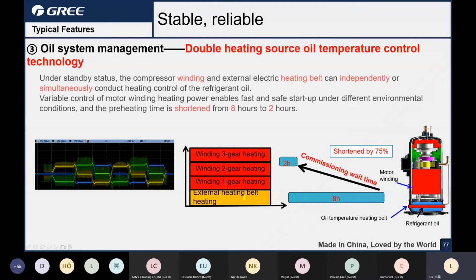However, in GMV6, not only the heating belt, the compressor can use the motor winding. You can see here, the compressor can use the winding to generate the heat like a heating belt. It can use the winding 1 gear, 2 gear, 3 gear, depends on the environment. So actually, the preheating waiting time can be shortened to 2 hours. Okay, that's very convenient, right? Especially for your commissioning job. Okay, that's the oil preheating.